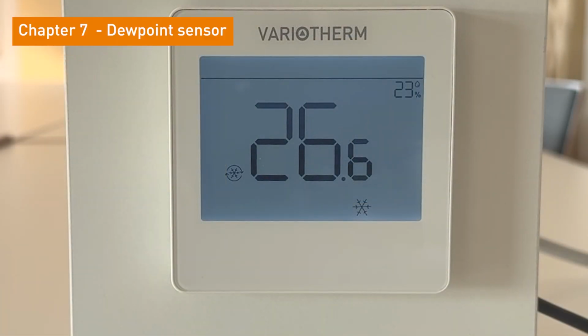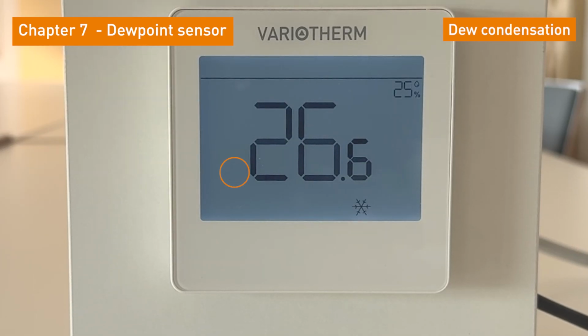Chapter 7. Dew point sensor. The room thermostat can also be used with the dew point sensor. When the dew point sensor is activated, the following conditions are possible: active, dew condensation, and fault. If the status is dew condensation, cooling is interrupted and the cooling on signal flashes.